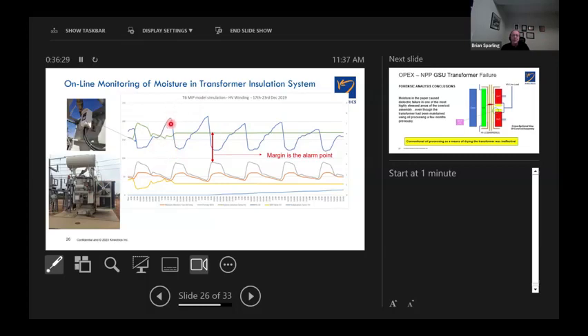What we see here in blue is the measurement of relative saturation of moisture in the oil. And the scale here is around 4% to something over 7% saturation. But you can see it's cyclic, it's going up and down. The gray is the primary winding hotspot temperature calculated by measuring oil temperature and load using the equation. It's close to 100 degrees C. It's hot. And in orange is the top oil temperature of the transformer.